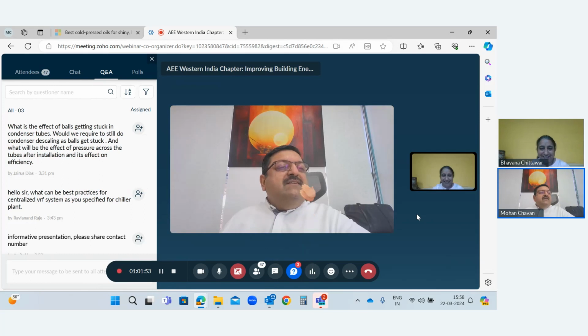So for this, let's say I would answer briefly, because when this system is commissioned, we need to do a proper descaling, and the tubes need to be checked thoroughly for cleanliness. So once we do that properly and commission the system, the balls don't get stuck inside the tube. And another important point is every 3 months we have to change the balls. If you don't change the balls after 3 months, then there is a possibility that the balls may get stuck inside. So if you follow the proper guidelines from the manufacturer, we don't see any issue as such, balls getting stuck inside. Because I have seen these systems working in the field now for over 10 years. And there are installations wherein for 4-5 years, no descaling was done. Okay. Hope I could answer the question, right?